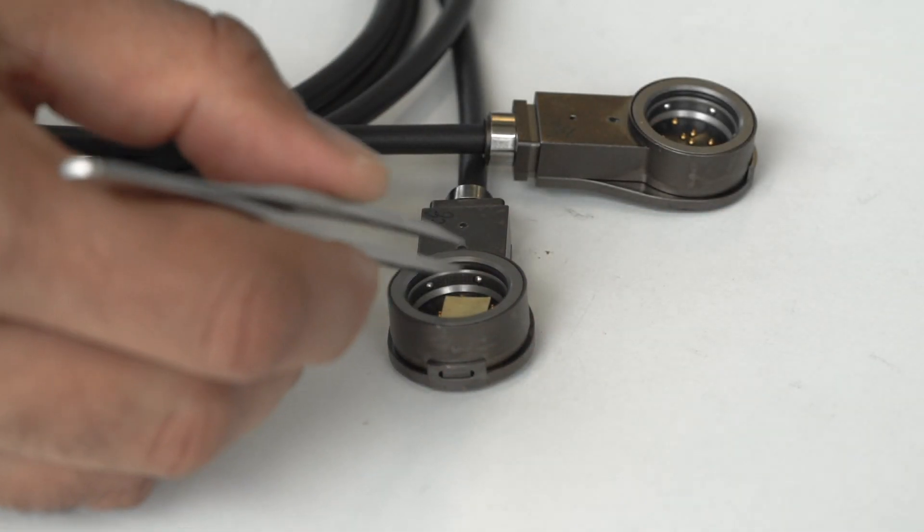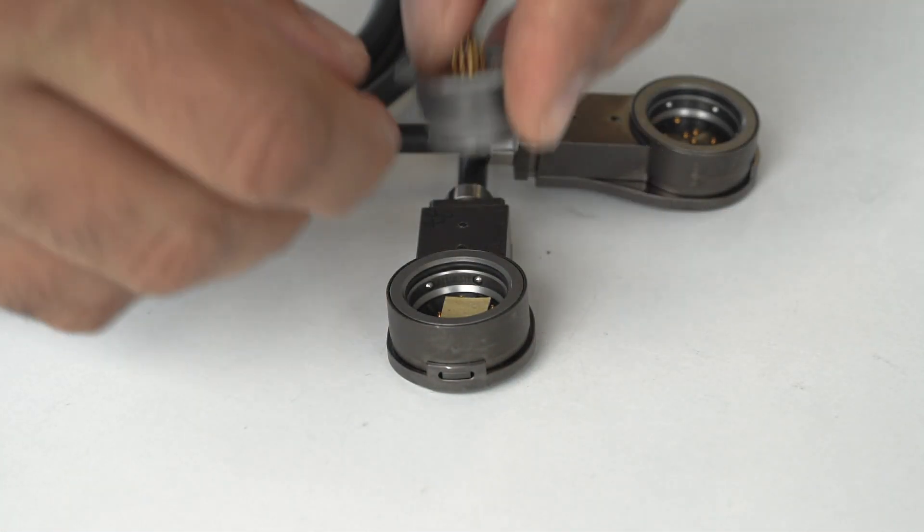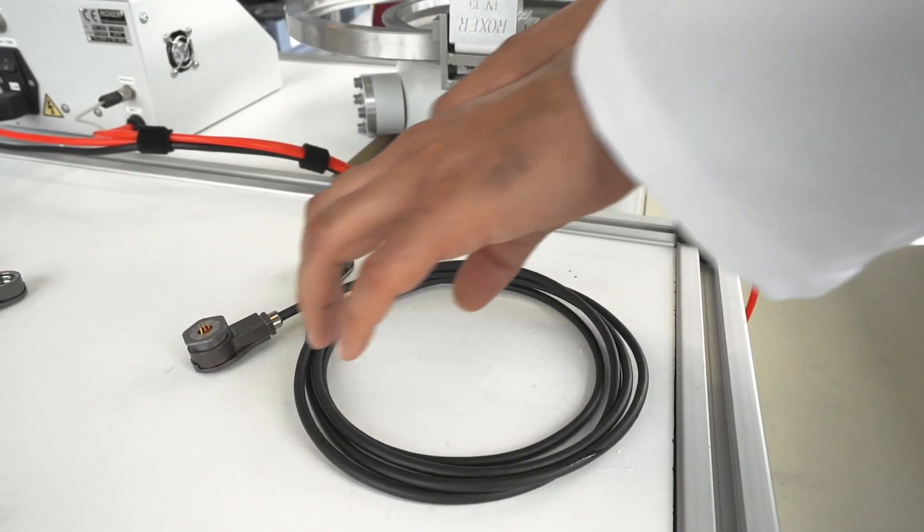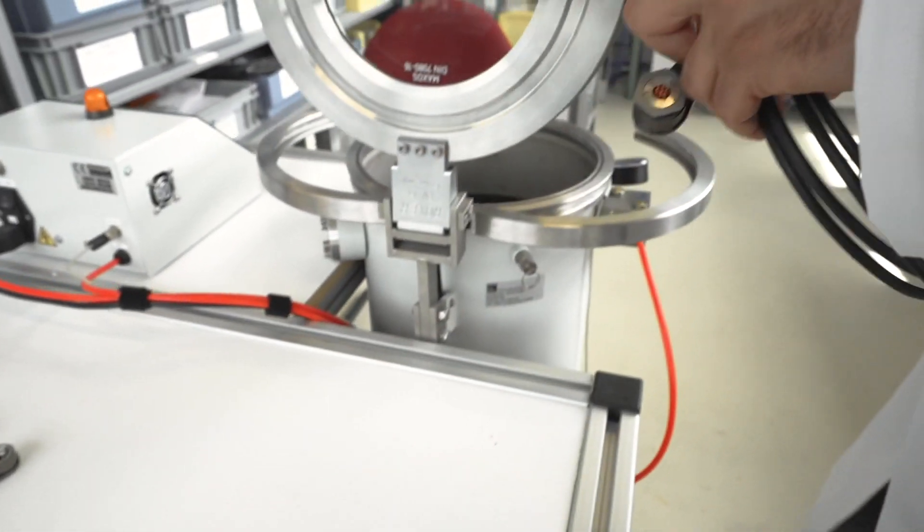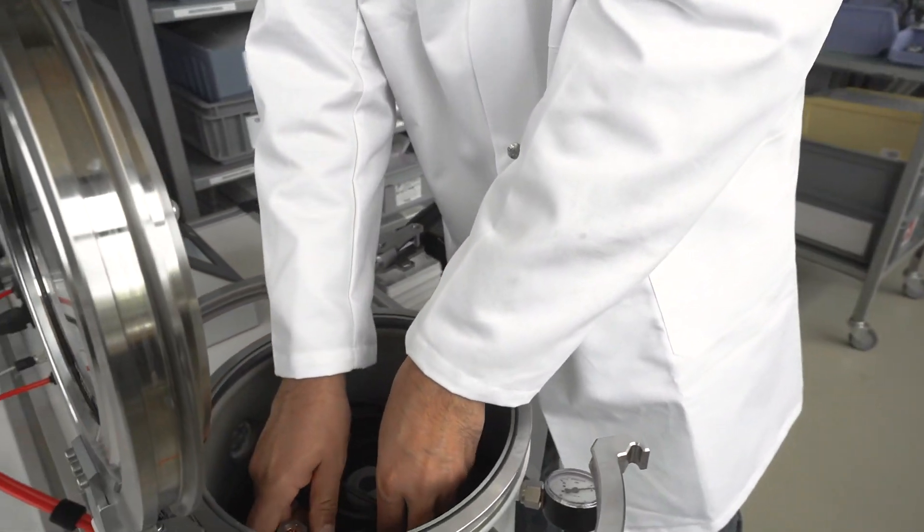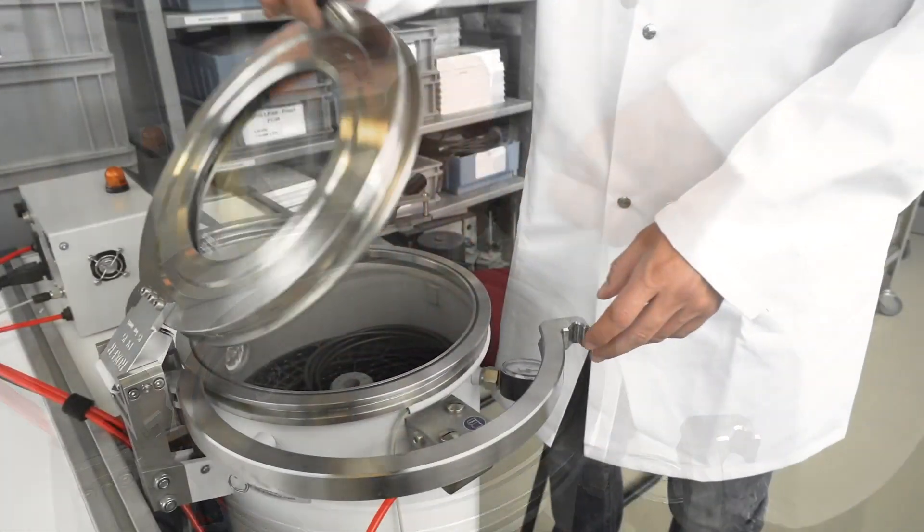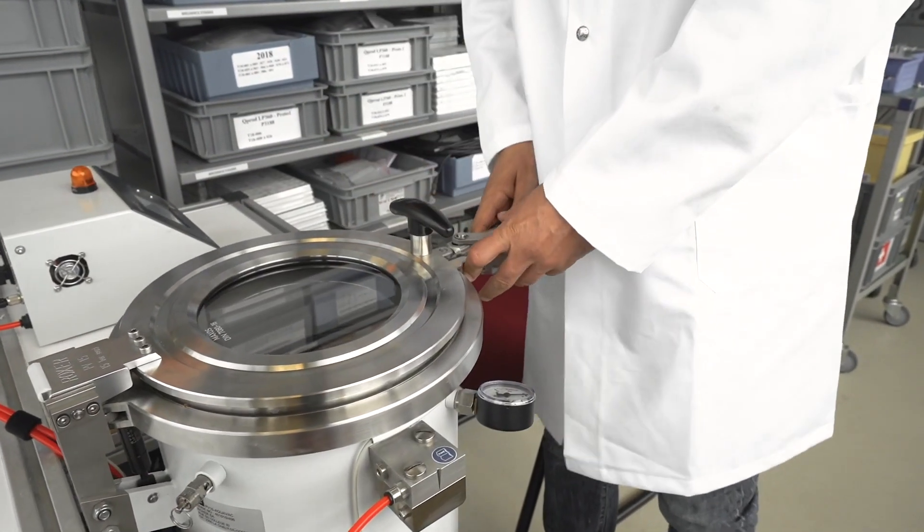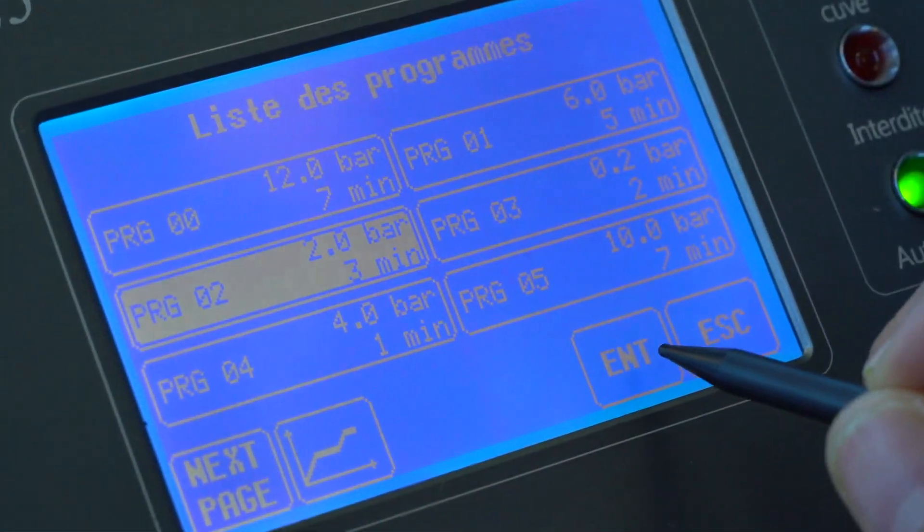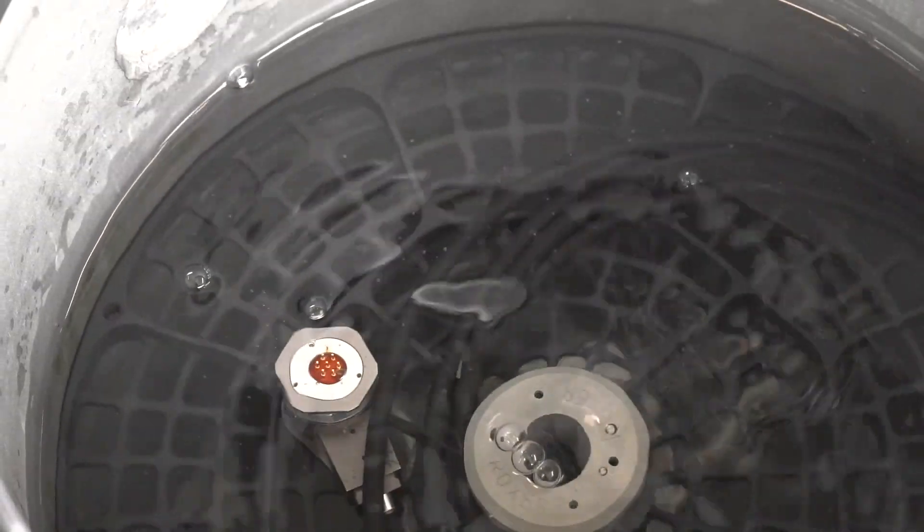Due to its sealing performance, the Fischer Freedom Series is the ideal connectivity solution for extreme environments. A small pH indicator paper is placed between the plug and receptacle. The connectors are unmated and then immersed in water inside a pressure vessel at two bars, which corresponds to an immersion depth of 20 meters.